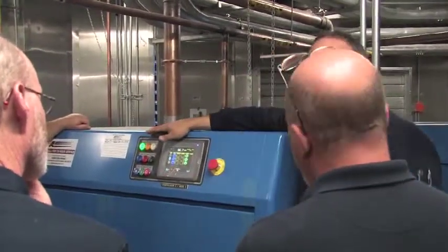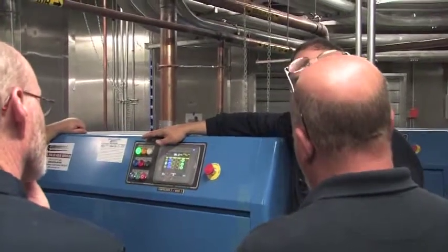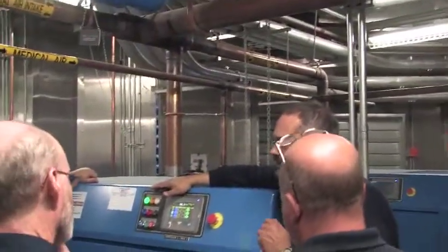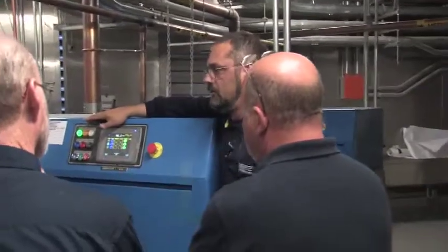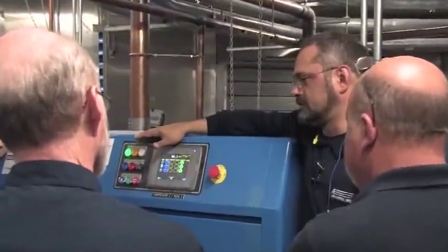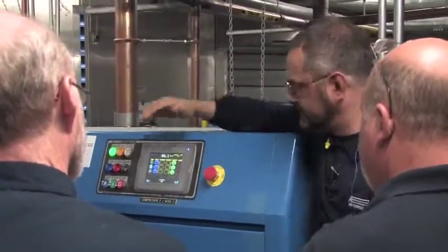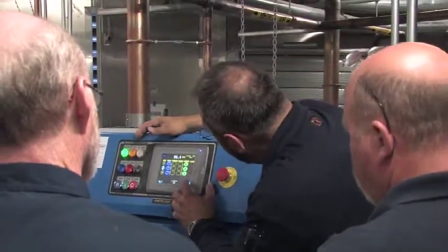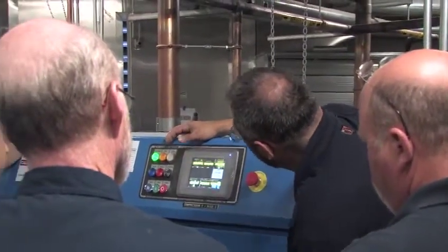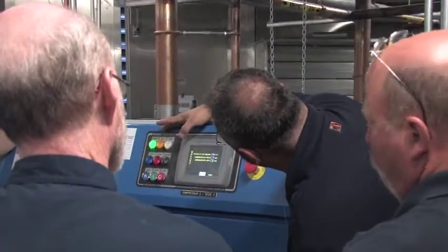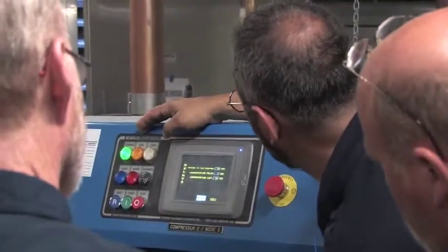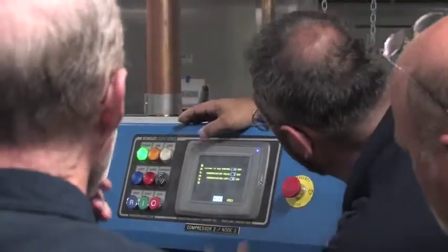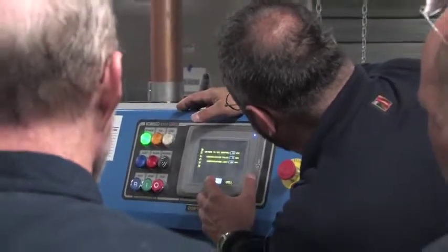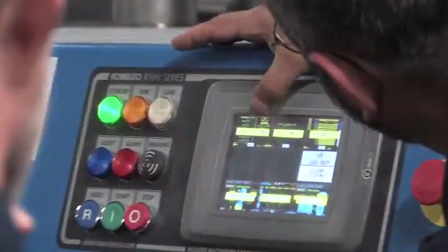Now, if you take a unit out of the sequence, then you can do whatever you want. If one's out, and if you take it out of remote mode, then the sequencer knows it's out of remote, so the sequencer will bypass it. It'll tell you it's not. So let's look at what's going on in the sequencer. We're just not supposed to make changes to the others.